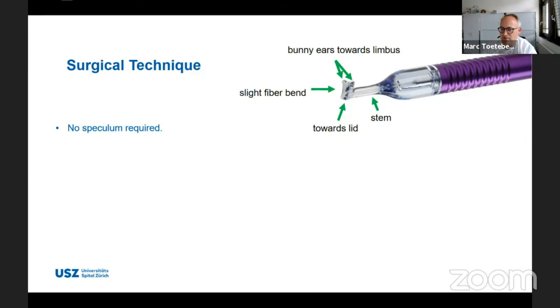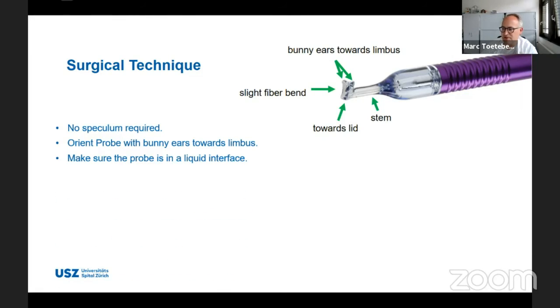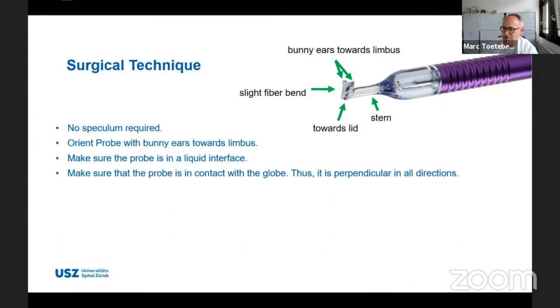The stem gives you enough access for the eyelid to see the limbus around the area where you want to treat. You orient the probe with the bunny ears towards the limbus. Make sure that the probe is in a liquid interface, and I come back to that later. Make sure that the probe is in contact with the globe. It's basically, if you use a pen and you write your signature on a piece of paper, the same amount of pressure you need to guarantee that the device with a laser fiber is in contact with the tissue you want to treat.